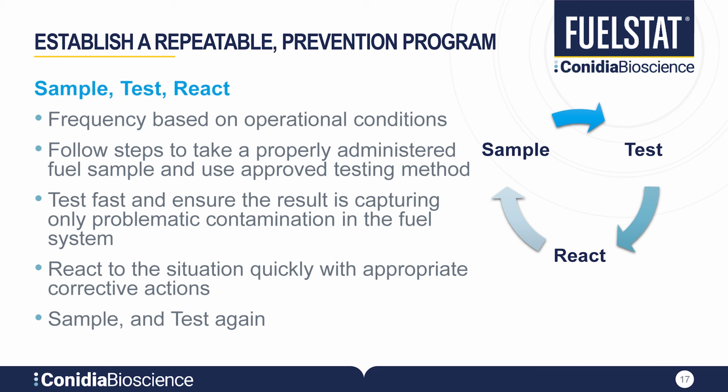However, any process should consider the key elements of preparation, environment, sample, and transport to ensure that the sample is the best that it can be, helping to maximize the chances of obtaining the most representative result from any testing process. Speed of testing is vital, but the most important factor is the removal of as much water as possible from the fuel system to minimize both the risk of microbiological contamination and indeed the cost of fixing a problem.